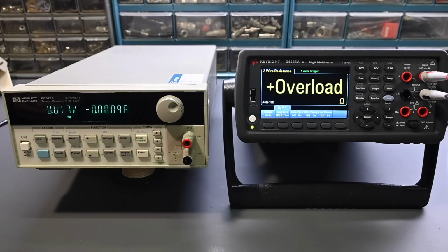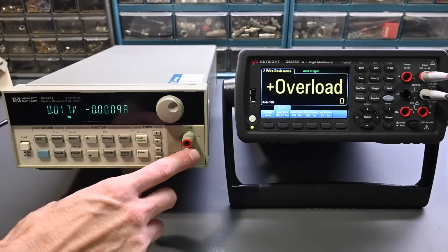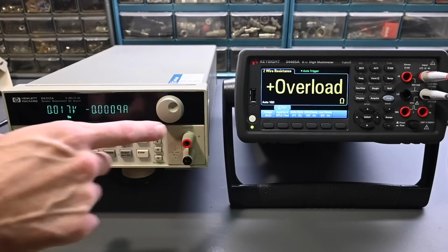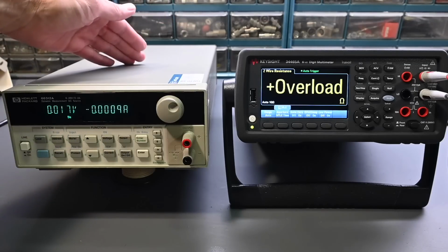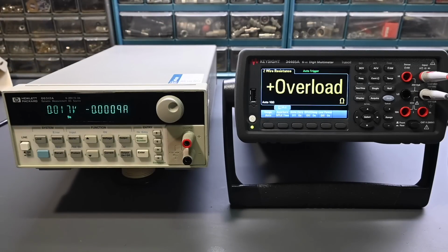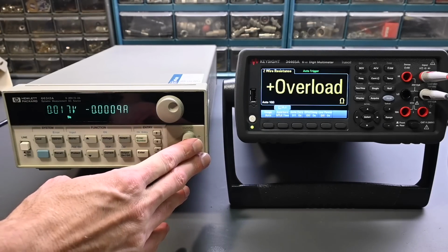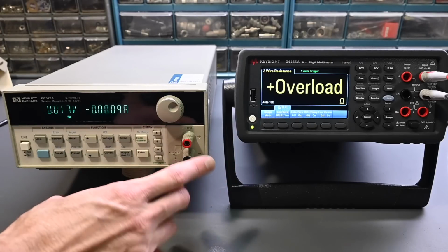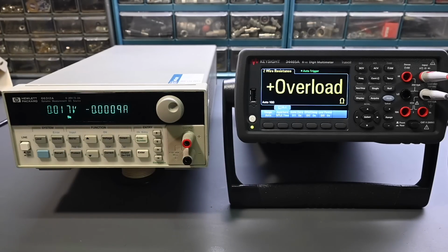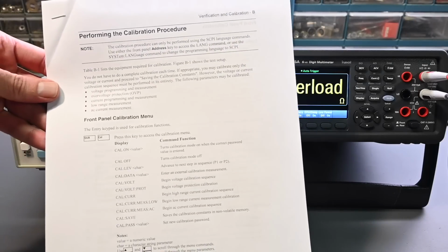as accurate as possible. And the reason I think that they don't want you to do the calibration on the front panel output is because there's about a foot of wire that goes from these terminals to the circuit board, and that can't be compensated for. There could be some losses in that wiring. And on the rear panel output, you have the remote voltage sensing, and the accuracy is spot on right at those terminals because of that remote voltage sensing. But nonetheless, I think it'll be perfectly fine to do at least a first run through on the calibration using the front panel output. And the steps for the calibration right here in this manual, I just printed them off.